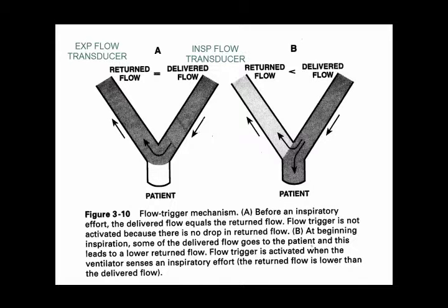Downside to it. What if we have a cuff leak? It's going to keep on triggering all by its lonely self. In the face of leaks, flow triggering can be problematic. And I've seen patients self-cycle.